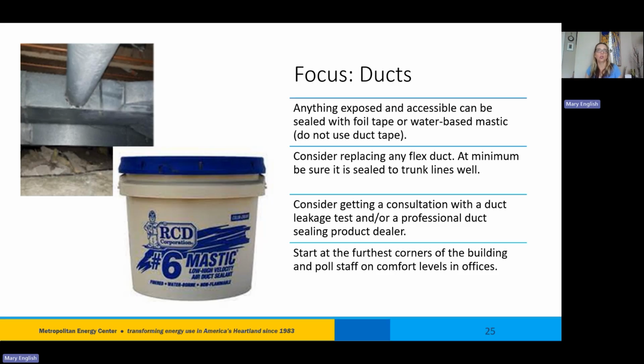That's because all that expensive air is leaking out on the way to those rooms. You really need to make sure any exposed ductwork you can access easily gets retroactively sealed. You do that with UL 181 foil tape, a really great product, but it's more expensive than what I have pictured here, which is water-based mastic - cheaper, and can be painted on like a brush. It gets a little messy, but it's very worth it to access those ducts and air seal around every seam. You can see holes in this connection with the duct to the trunk line - all of those are leaking out copious amounts of air.